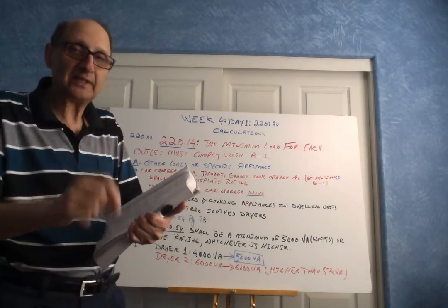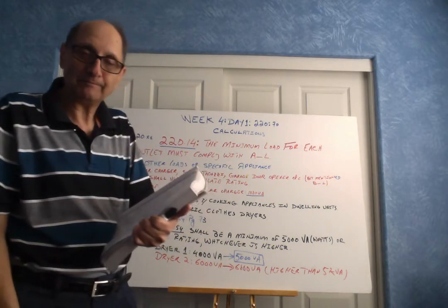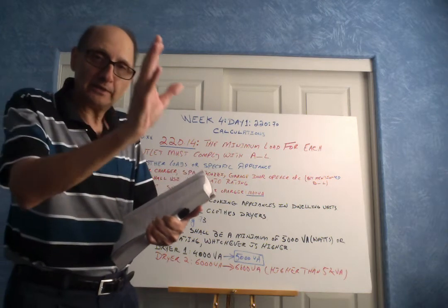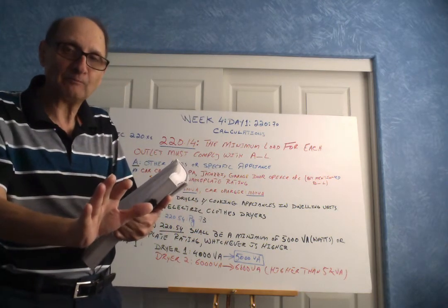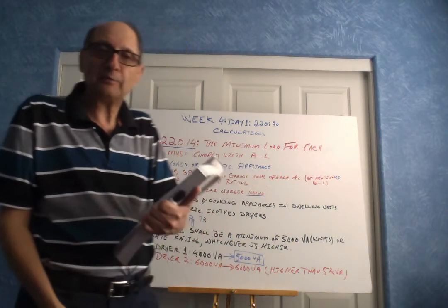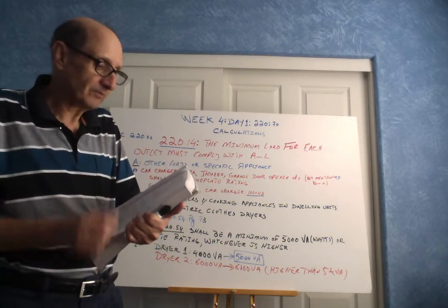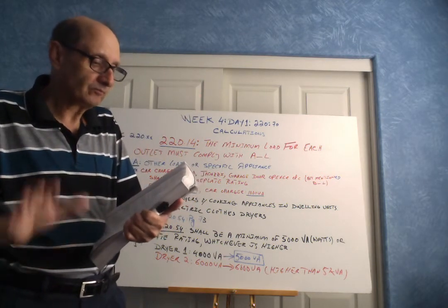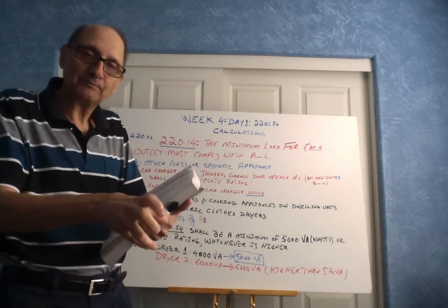What that means is that you add all of them up, then you multiply that by 0.85, and whatever value you get from the product, you use it. If you have up to 4 dryers, then you add them up and you use the entire value.